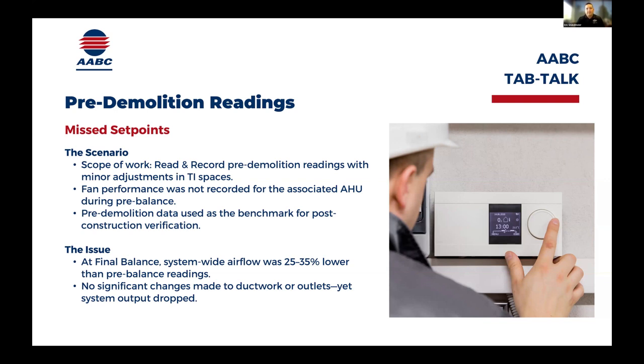They did the work, we came back, and we were 25 to 30% lower on all of our diffusers. Of course, you point to the air handler, assuming it must not be operating at the same RPM or static. Something must have happened to it. But we didn't have the readings. We didn't go up and take statics, didn't take a snapshot of the BMS, didn't know what the RPMs were. We had no way to reestablish what the air handler was doing pre-balance, because it wasn't identified in our scope of work.